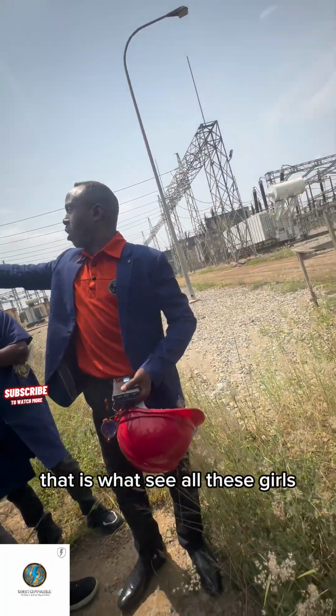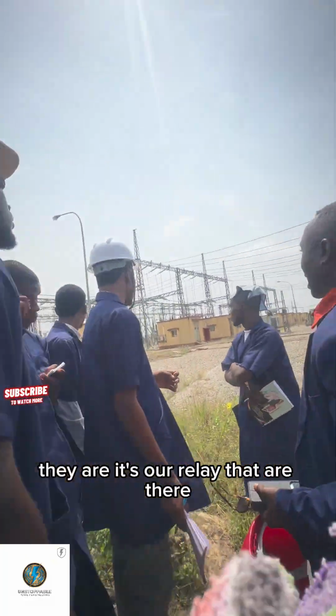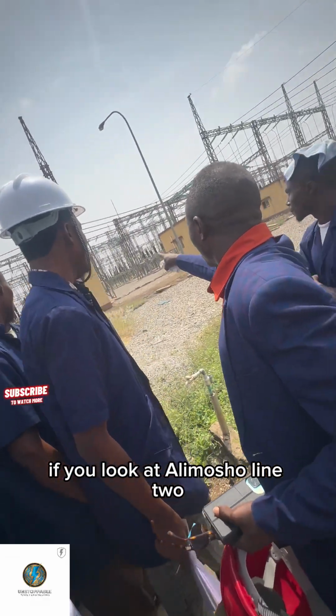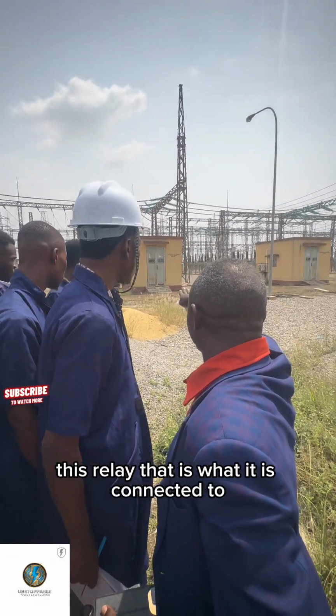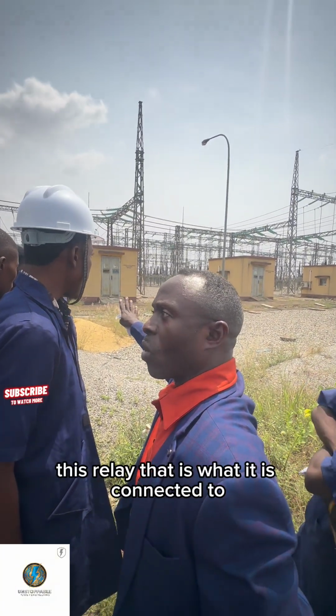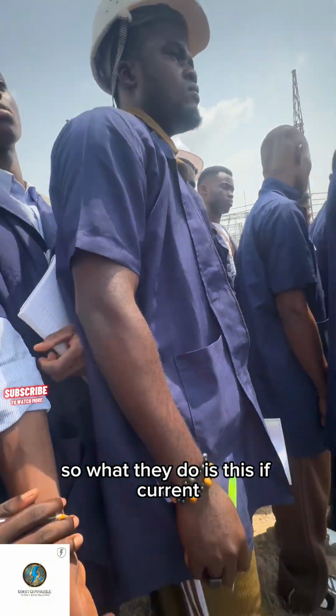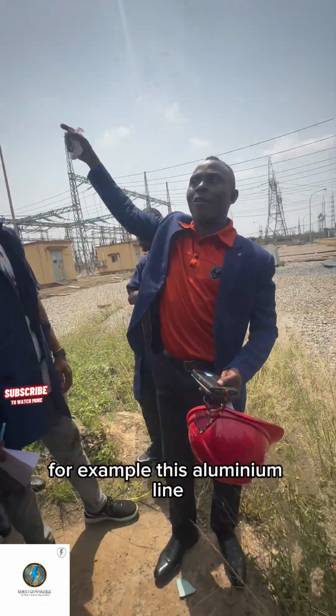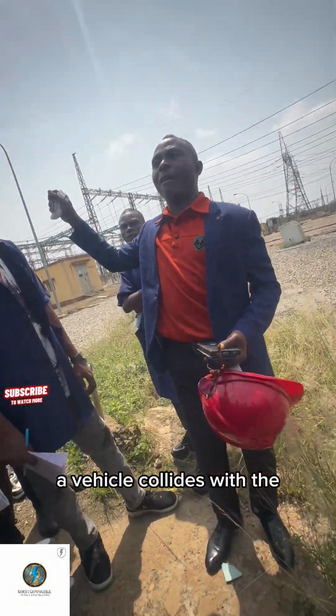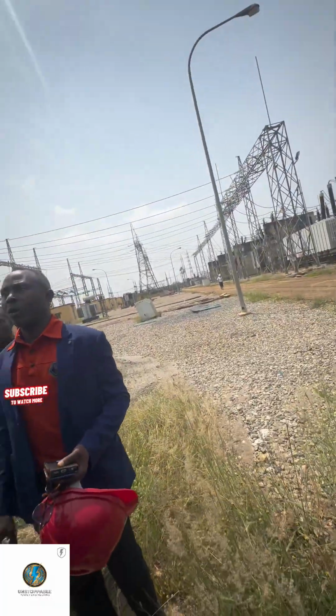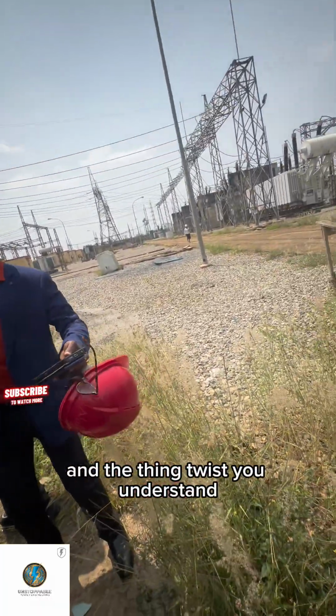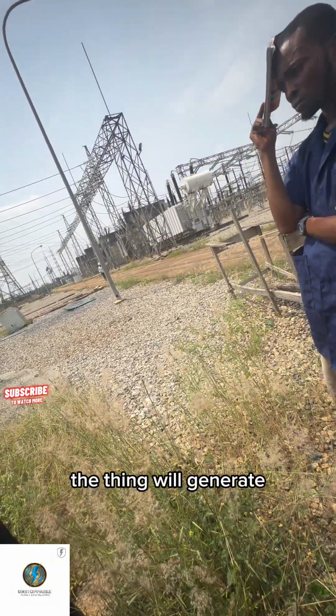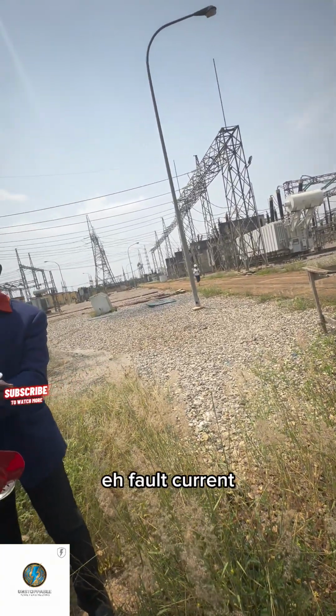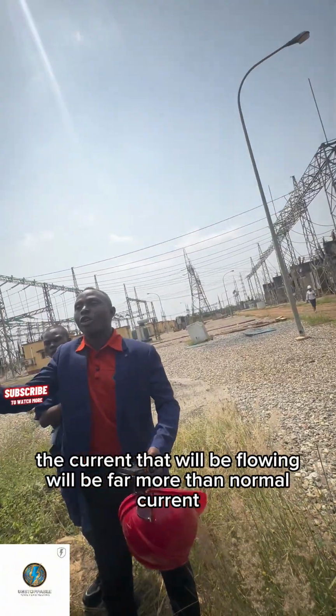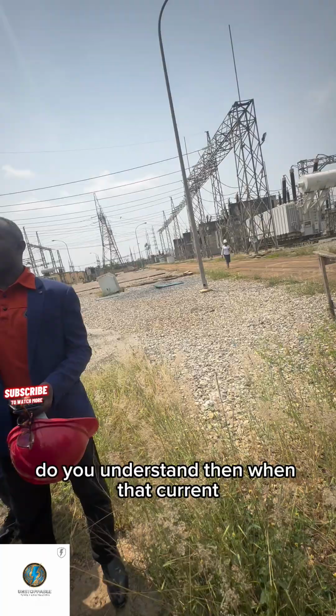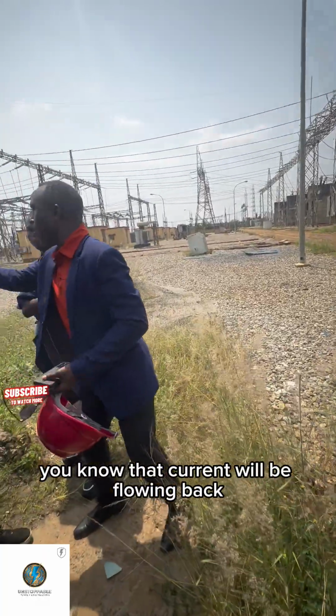See, all these kiosks, it's our relays that are there. This relay now, if you look at Alimosho line 2, Alimosho line 1, this relay is what it is connected to. So what they do is this. If there is any fault on the line, for example this Alimosho line, a vehicle collides with the pole, you understand? And the thing twists, the thing will generate fault current. The current that will be flowing will be far more than normal current.